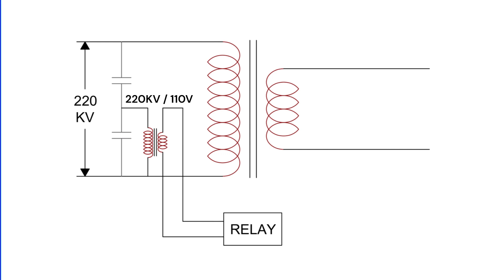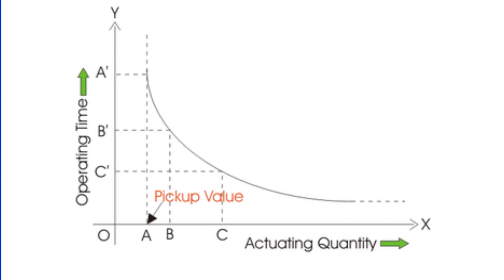Now, does this mean the transformer will trip instantly at a V over F ratio of, say, 2.5? Not necessarily. The core can tolerate overfluxing for a short duration. That's why overflux protection uses an inverse time characteristic. The higher the V over F ratio, the faster the relay will trip.